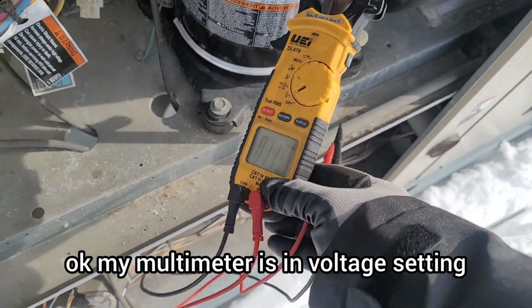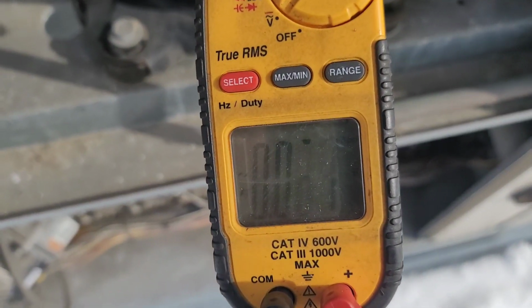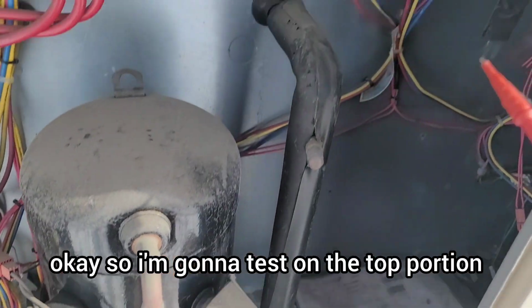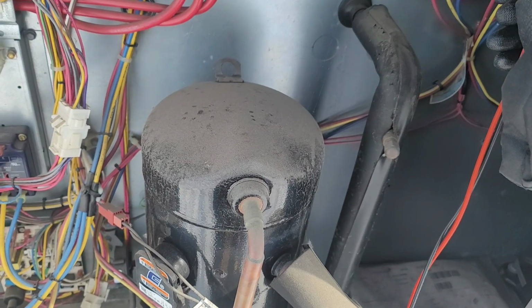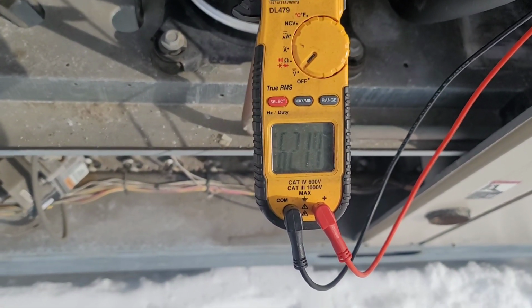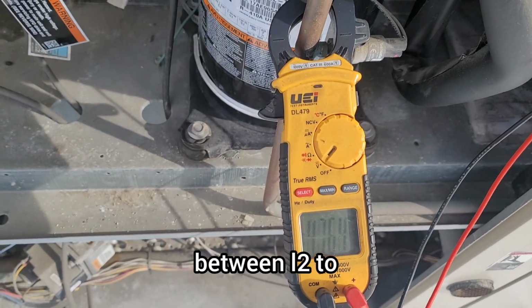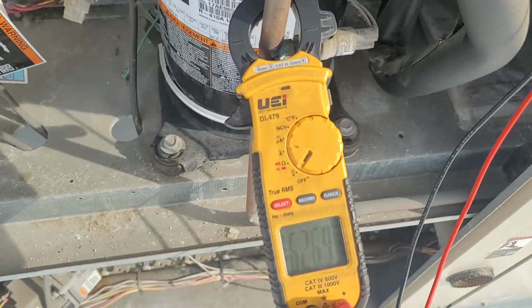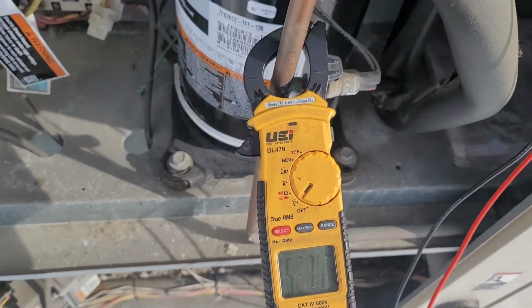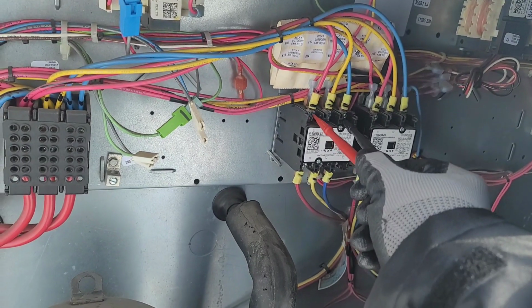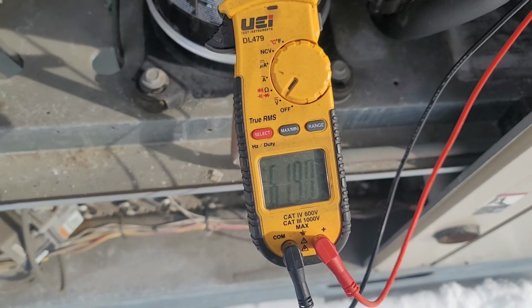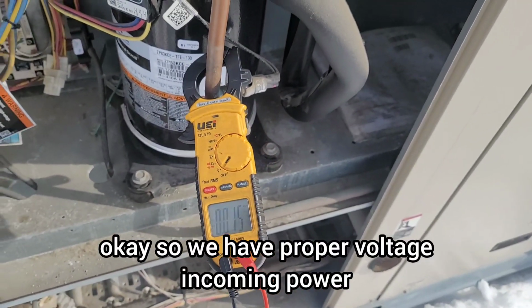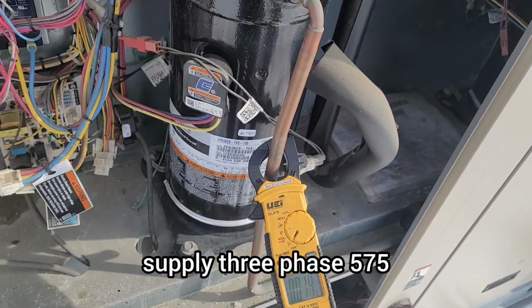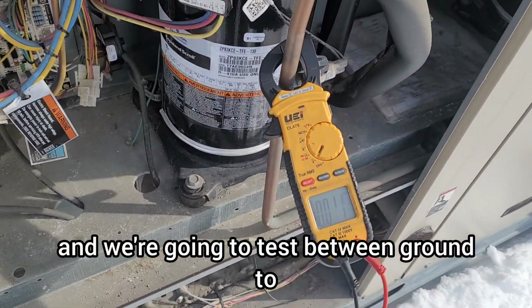Okay, my multimeter is in voltage setting, you can see. Just bear with me. Okay, so I'm gonna test on the top portion of this contactor between L1 to L2. 620 something. Between L2 to L3, 627. Between L1 to L3, 620.